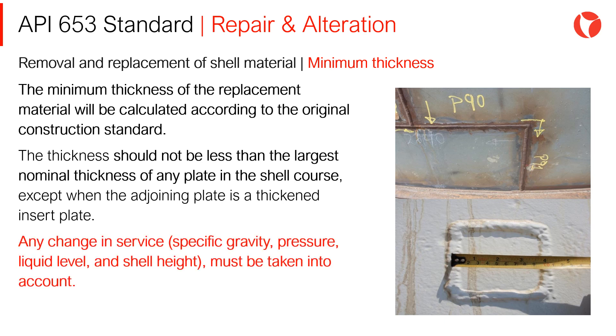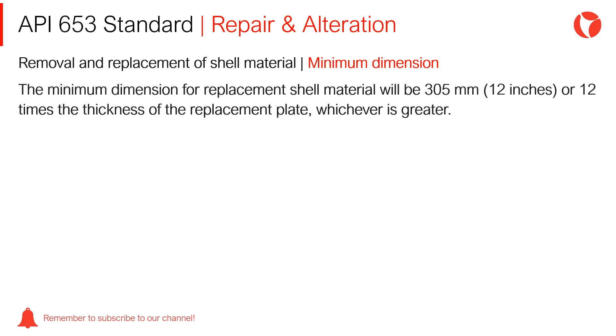Any change in service, specific gravity, pressure, liquid level, and shell height must be taken into account. The minimum dimension for replacement shell material will be 305 mm, or 12 times the thickness of the replacement plate, whichever is greater.